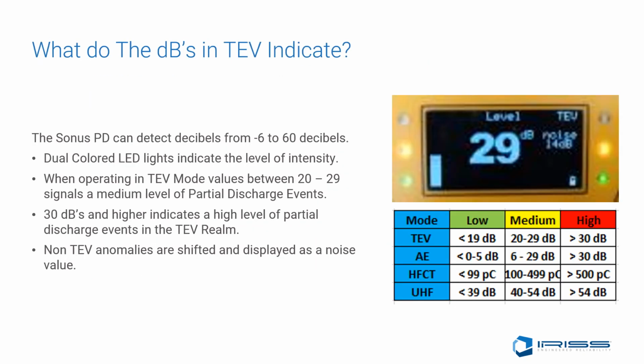The Sonus PD can detect decibels from -6 to 60. Dual-colored LEDs indicate the intensity level using green, yellow, and red lights. When operating in TEV mode, values between 20 to 29 signal that a medium level of partial discharge event is occurring. 30 decibels and higher indicates a high level of partial discharges occurring in the TEV realm. Non-TEV anomalies are shifted and displayed as noise on the screen.